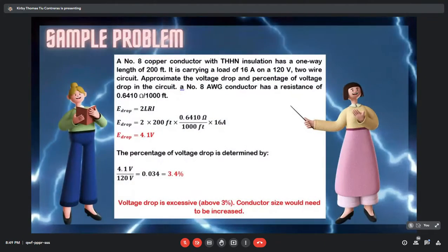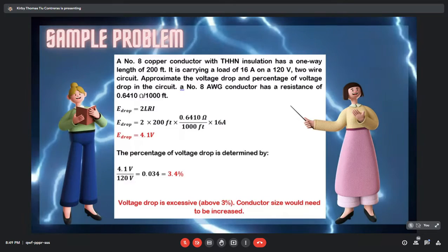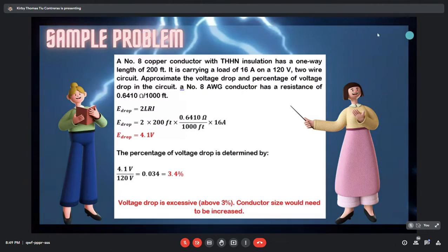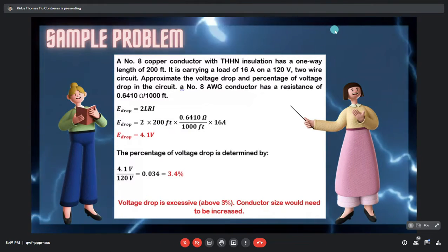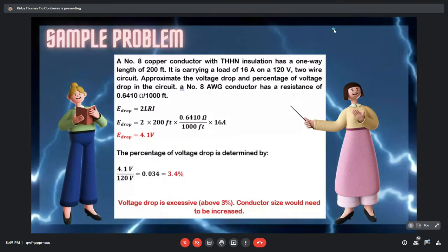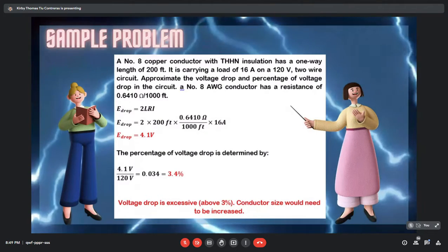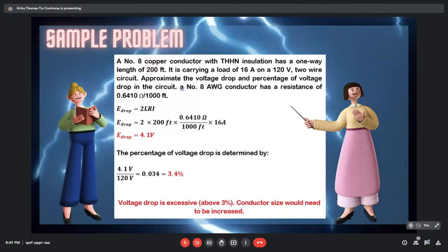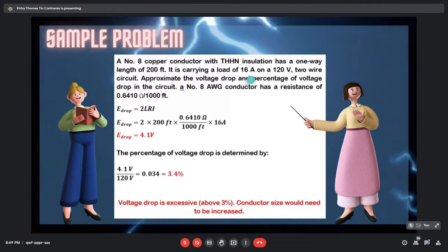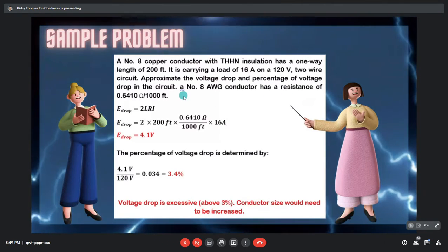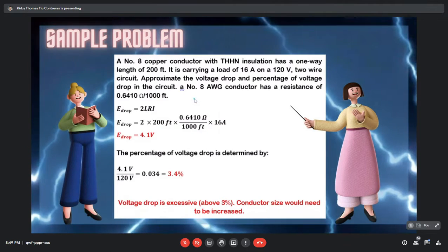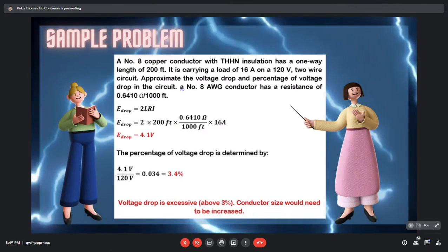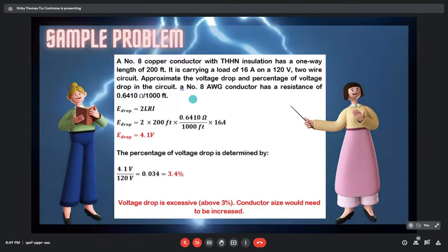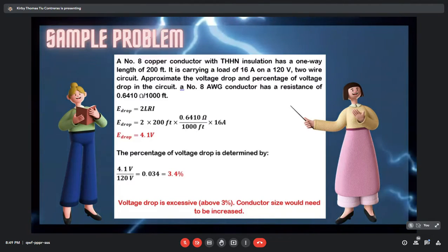For the example of this topic, a number 8 copper conductor with THHN insulation has a one-way length of 200 feet. It is carrying a load of 16 amps on a 120 volts two-wire circuit. Approximate the voltage drop and percentage of voltage drop in the circuit. A number 8 AWG conductor has a resistance of 0.6410 ohms per 1,000 feet.